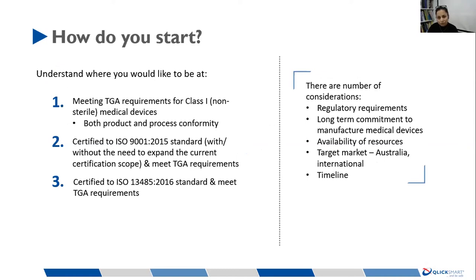The next step is to understand where you would like to be at the end of this process. So if you are producing a Class 1 device that is not sterile, you have to meet TGA requirements for both product and process conformity in your quality management system. For instance, do you have the processes within your company to set up and maintain technical files for the medical devices you're intending to place on the market?